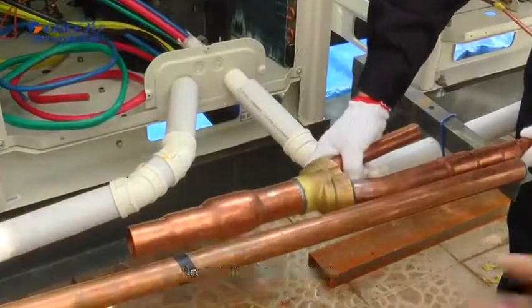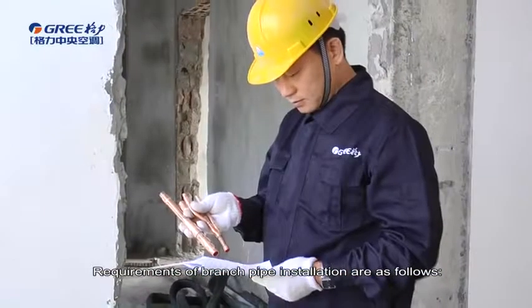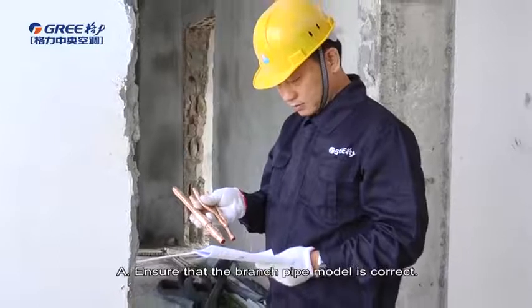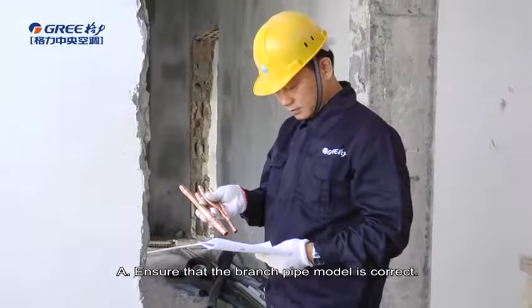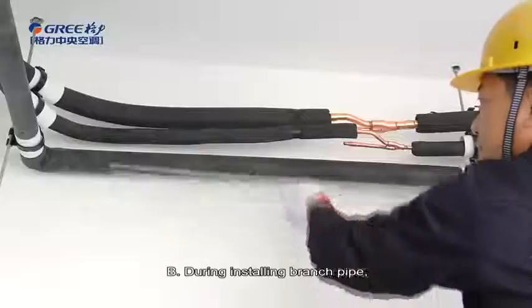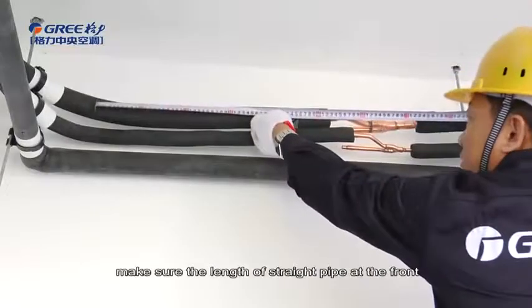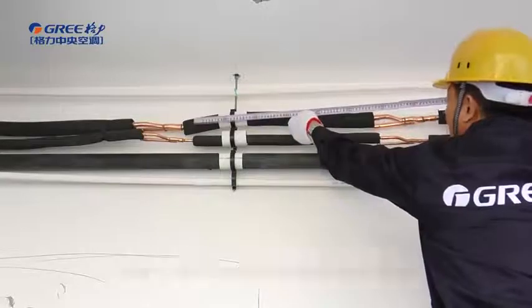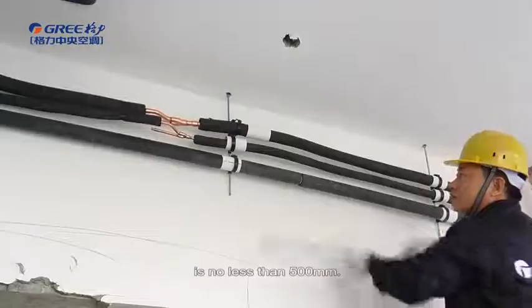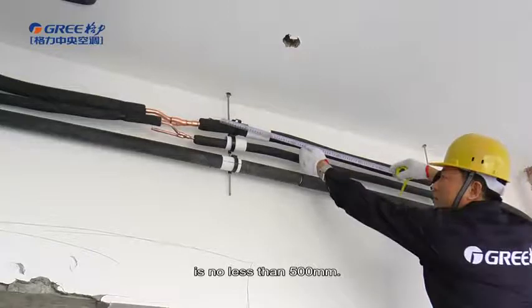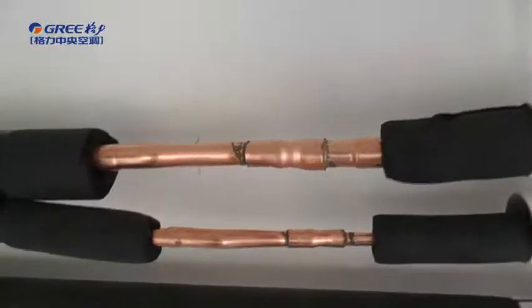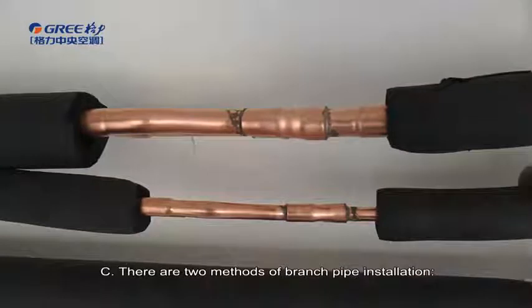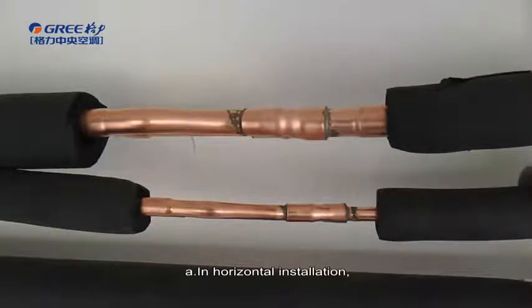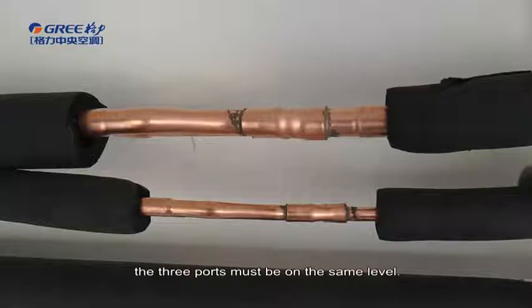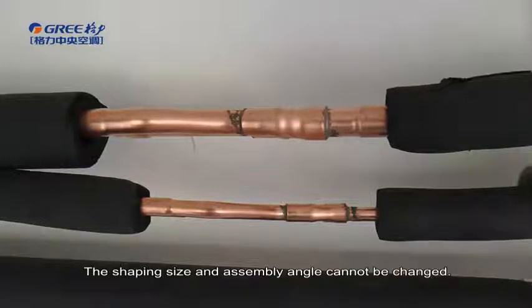Installation of branch pipe. Requirements of branch pipe installation are as follows. A. Ensure that the branch pipe model is correct. B. During installing branch pipe, make sure the length of straight pipe at the front and at the back of the 3 connection pipes is no less than 500 mm. C. There are 2 methods of branch pipe installation. A. In horizontal installation, the 3 ports must be on the same level. The shaping size and assembly angle cannot be changed.